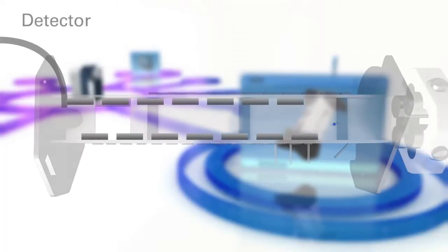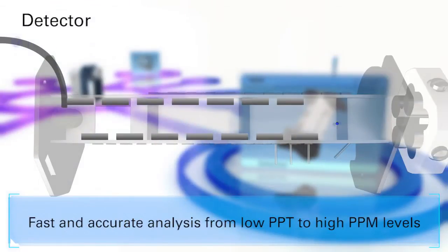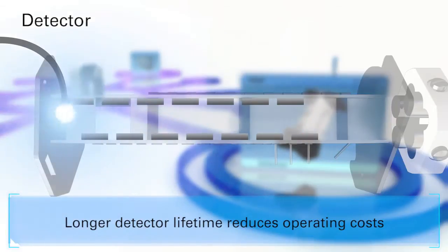Detector. The Aurora is the only ICP-MS to offer a fully digitized detection system, maximizing detector lifetime and providing more than nine decades of linear dynamic range in pulse counting mode. Longer detector lifetime.